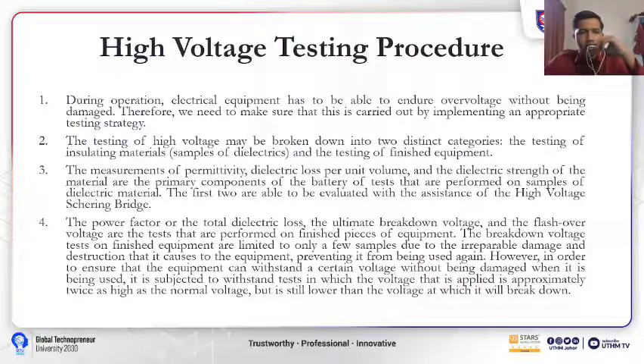Second, the testing of high voltage may be broken down into two distinct categories: the testing of insulating material samples and the testing of finished equipment. Third, the measurement of the dielectric loss per unit volume and the electric strength of the material are the primary components of the battery of tests that are performed on samples of the dielectric material.